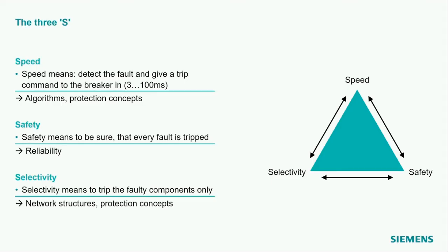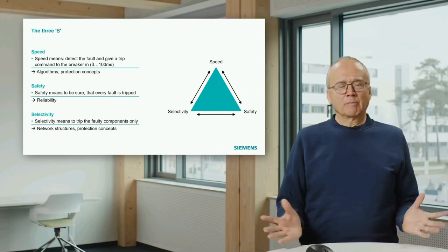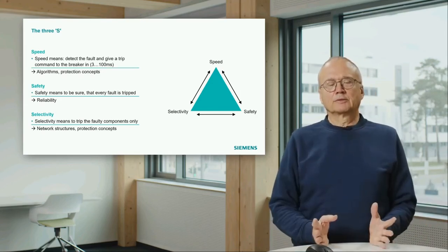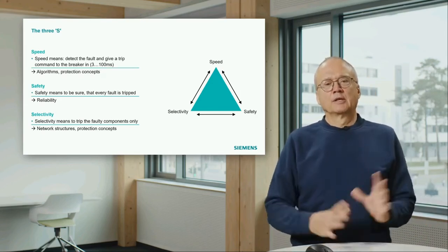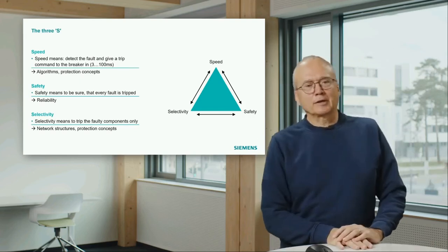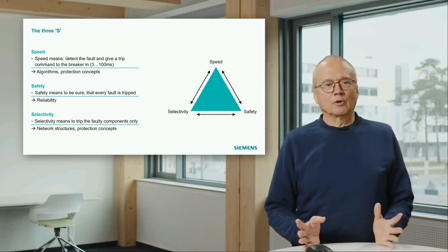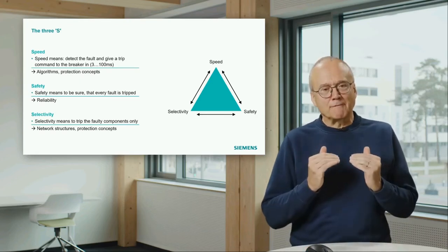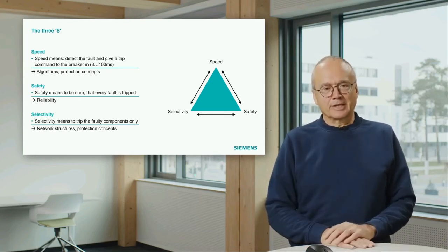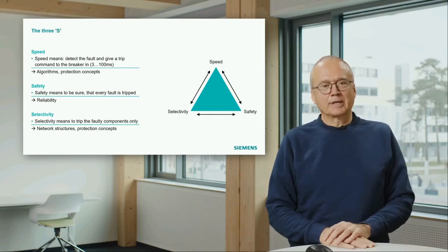Now let's talk a little bit about the requirements to protection, and there we often mention the 3 S. That means speed, safety and selectivity. So let's look at this a little bit more. What does speed mean? Speed is pretty important. Remember, short circuit, a lot of current flowing, risk of damage to components. That means we must be fast to disconnect the fault if we detect one.